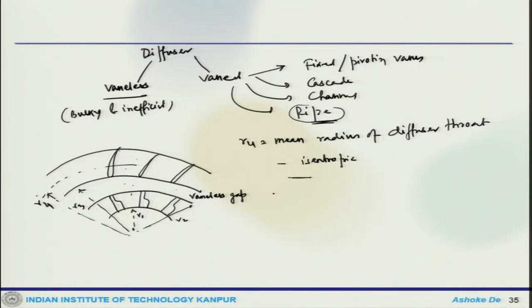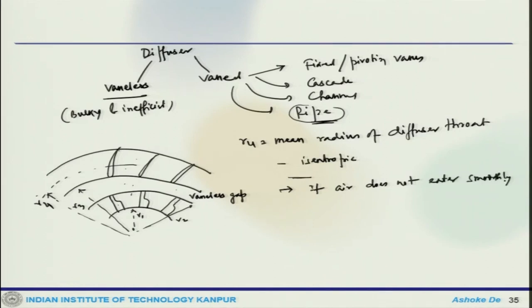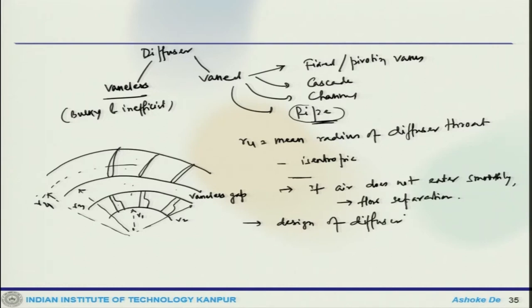Air will pass through these passages and finally we get the proper pressure rise. If the air does not enter smoothly, there would be flow separation, and because of the flow separation there would be performance degradation in the compressor. So, the design of the diffuser becomes important.